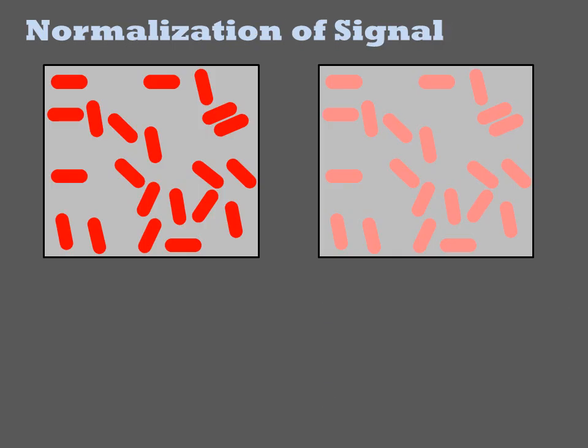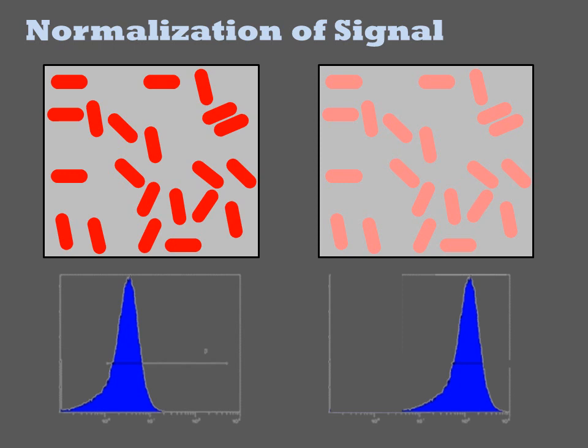Suppose I use my god's eye view of what's going on in two samples of bacteria encoding RFP. On the left, the cells are much more fluorescent than those on the right. On two different days, I run one of the samples on the cytometer and collect a histogram. Surprisingly, the instrument is telling me that the cells on the right are more fluorescent than those on the left. The problem here is that the sensitivity of the instrument will drift over time. There are dials you can tune that can make the sample be any number you want it to be. Thus, you must in some way standardize the signal to get consistent measurements across experiments.